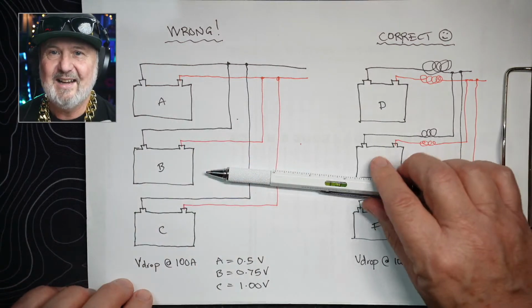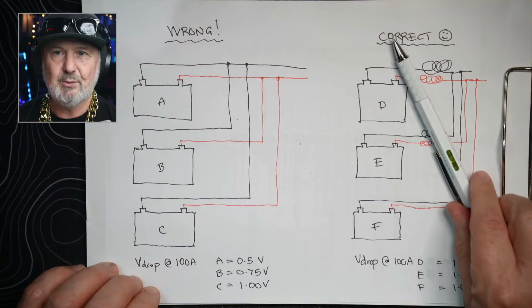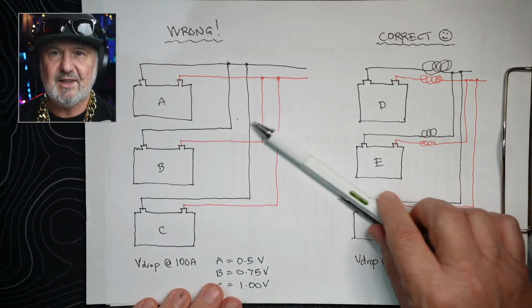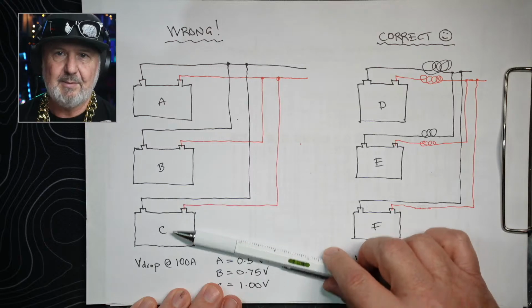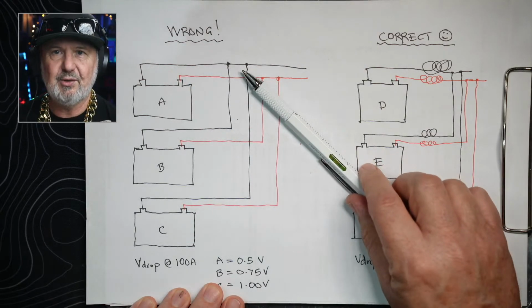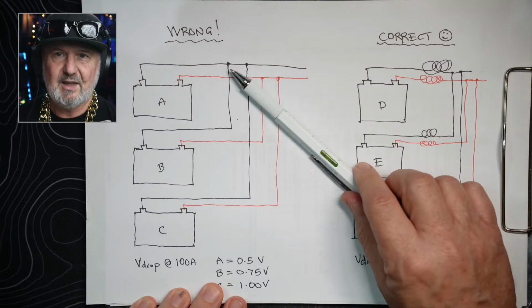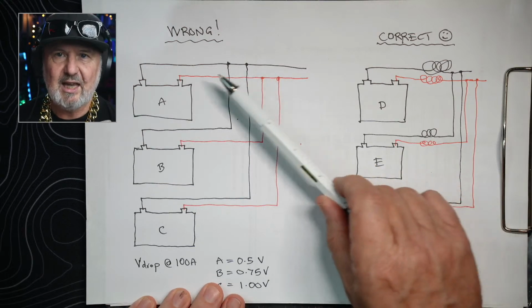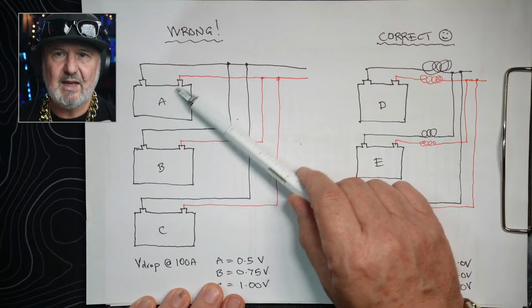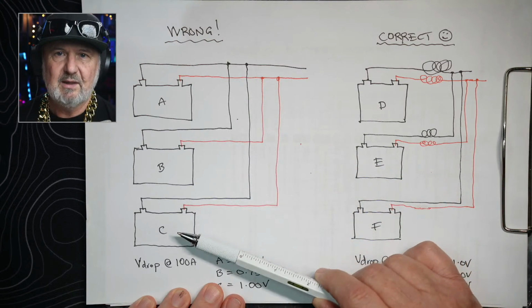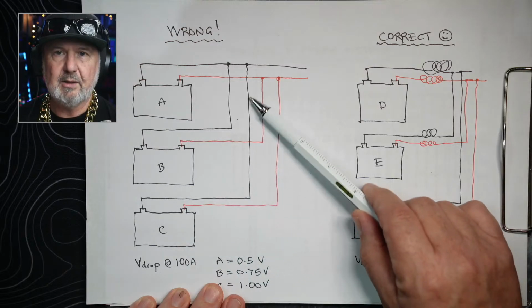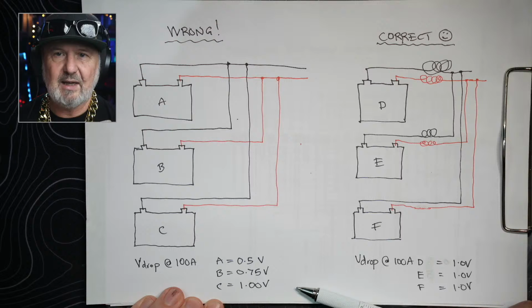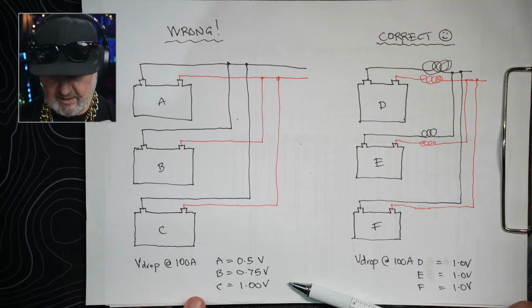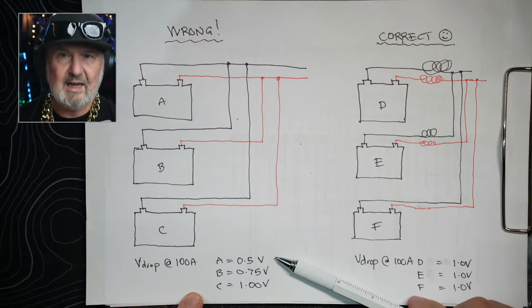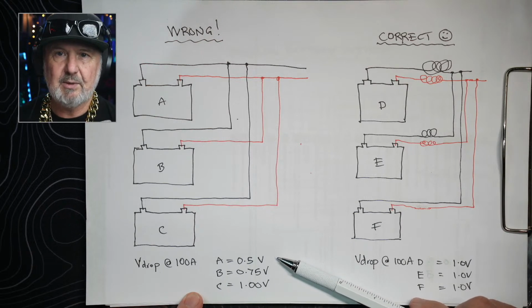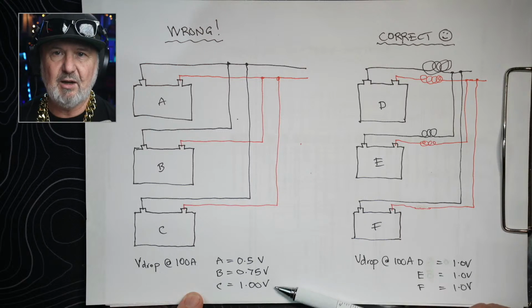That's pretty cool, eh? Anyway, what I want to show is wrong and right when you parallel battery systems. Now, it's very easy to think I've got 3 batteries here, A, B, C, and I'm just going to parallel them all onto a common point. Or let's say those little dots are all a common point. But when you measure the cables, they're all different lengths. Battery A is very close to the commoning point, whereas the worst case is battery C, a long way from the commoning point. And what you're getting is voltage drop under load. So voltage drop in this example, let's say at 100 amps, might get half a volt from battery A to the commoning point, 0.75 for B, and a whole 1 volt for C.